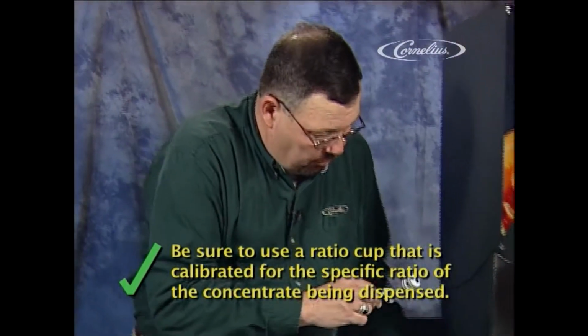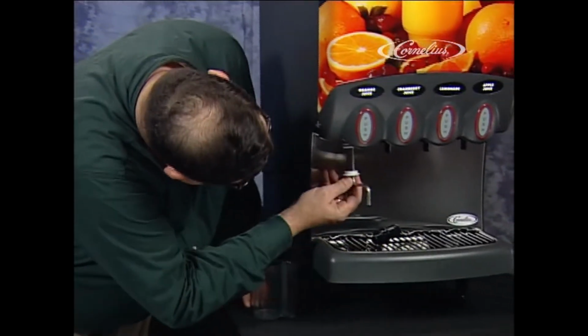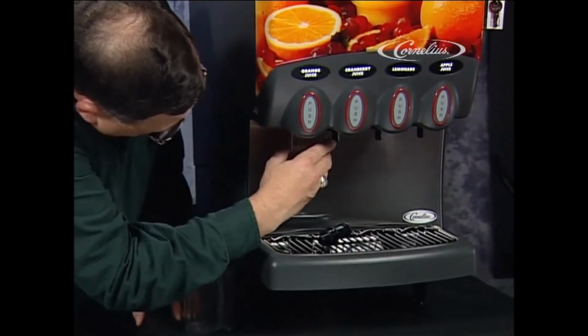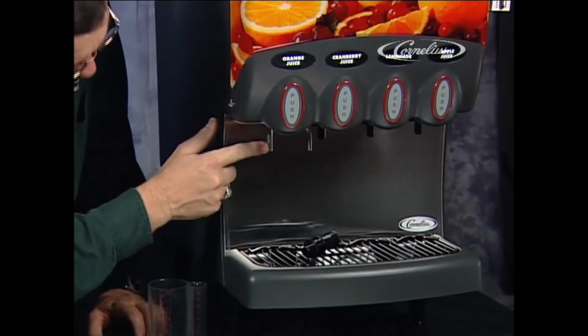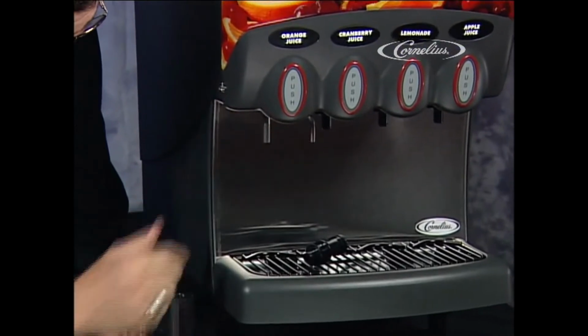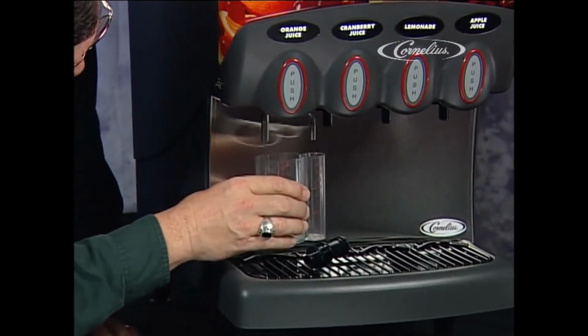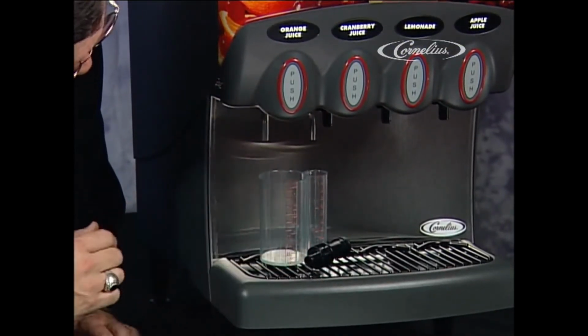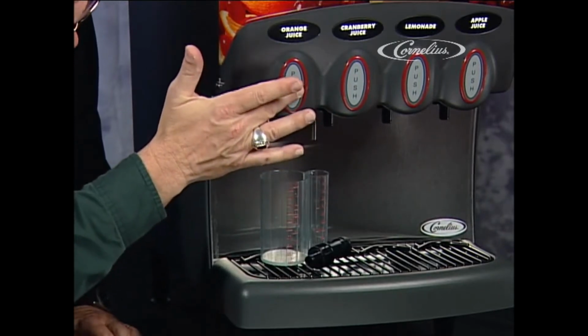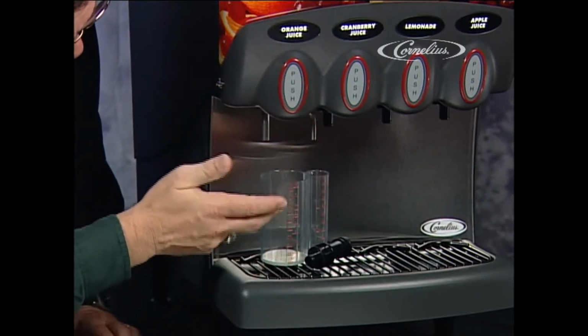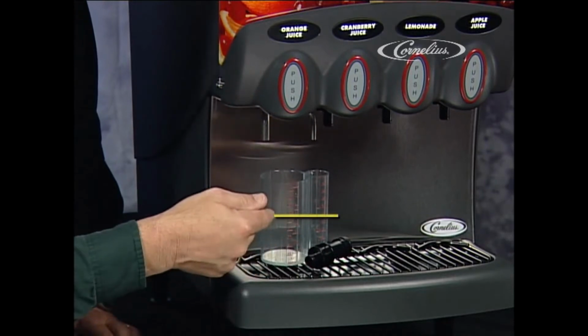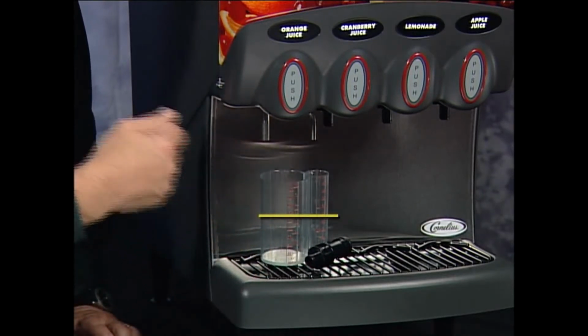With the nozzle removed, we insert the separator into the dispenser and rotate. The large tube will be the water. The smaller tube will be the concentrate. We then set the Brix cup underneath at the corresponding sides. We press and hold the button until we measure an amount. On a flat surface, where the line crosses the two line up is a proper ratio.